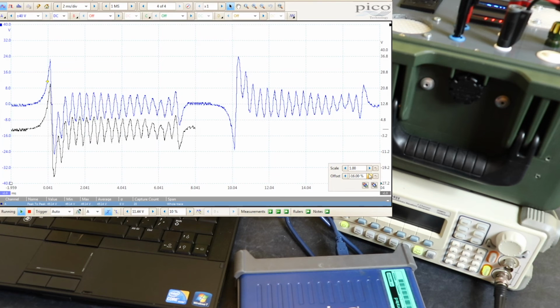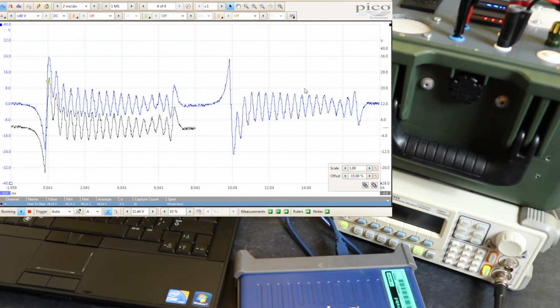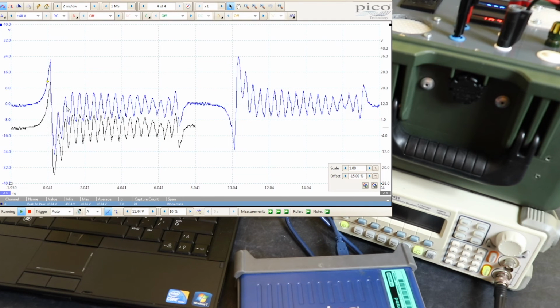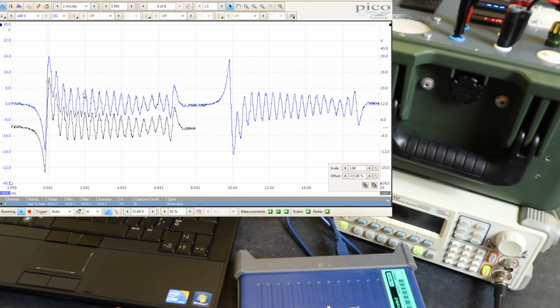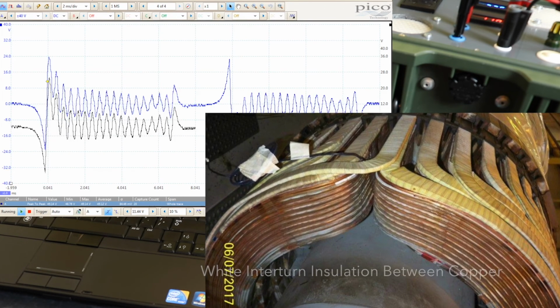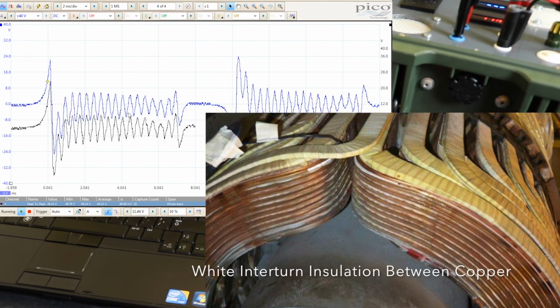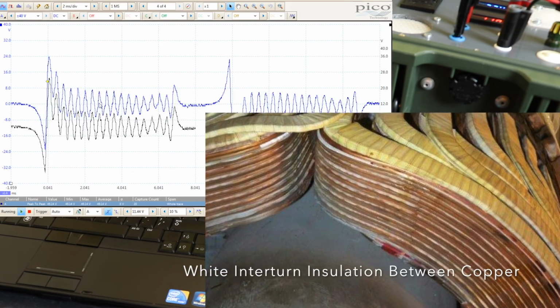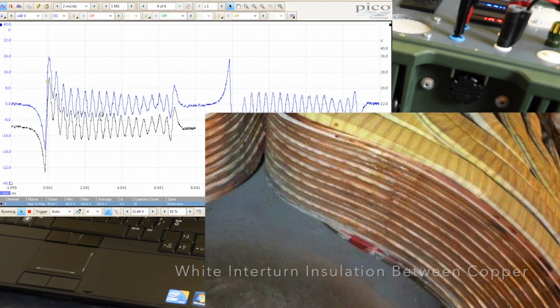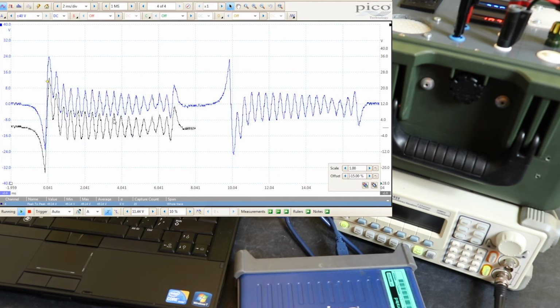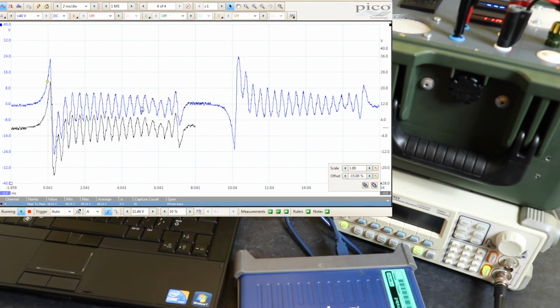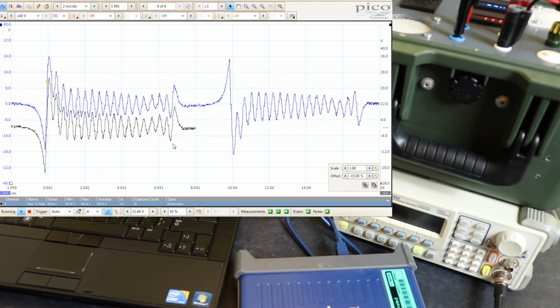The way you analyze this signal is that you compare these two halves. You take the second half, you flip it and invert it, and then you compare it, all these peaks, to the first half, which is what you can see is happening here. And then if there's a damage to the interturn insulation on the rotor, because this is what a flux probe does, it looks at the interturn insulation on a rotor winding, and if these peaks don't match or have over a 3% differential, then it's an indication that you've got damage of the interturn insulation and you may have problems with your rotor. So I can very easily create that formula within Picoscope, which is rare that you can do that in some of the other scopes.